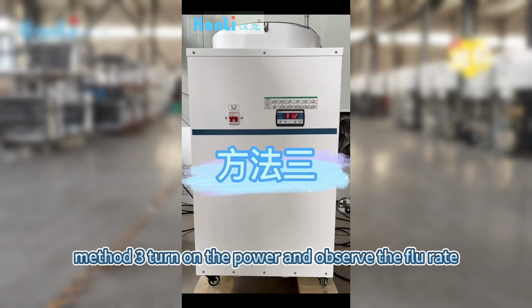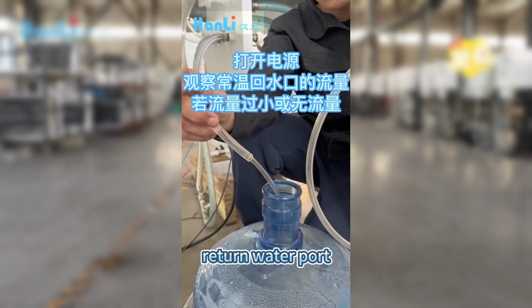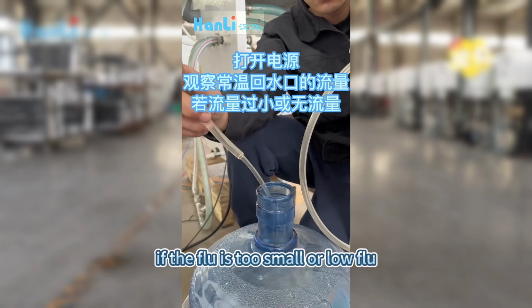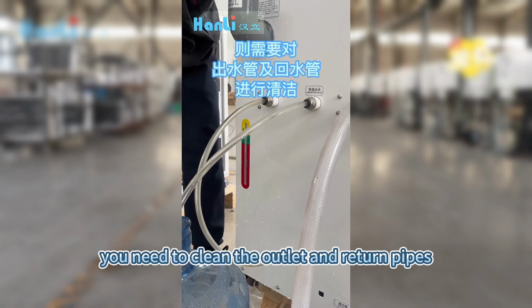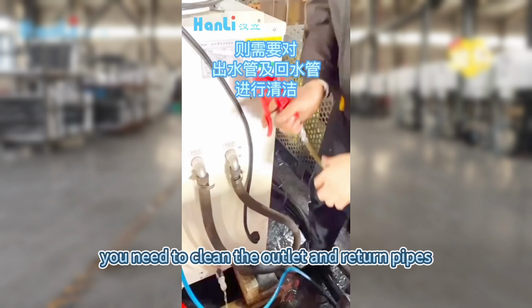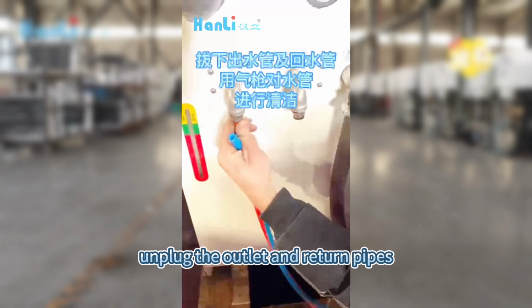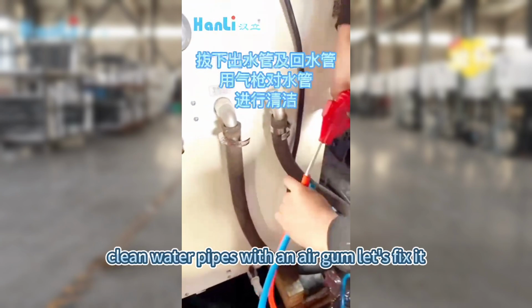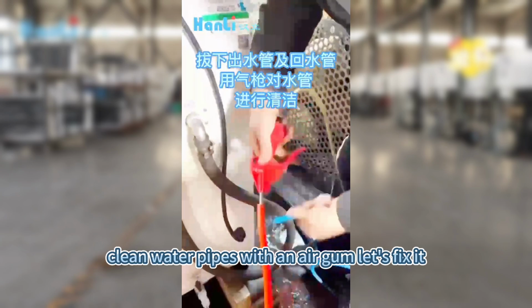Method 3. Turn on the power and observe the flow rate of the normal temperature return water port. If the flow is too small or no flow, you need to clean the outlet and the return pipes. Unplug the outlet and the return pipes. Clean water pipes with an air gun. This fixes it.